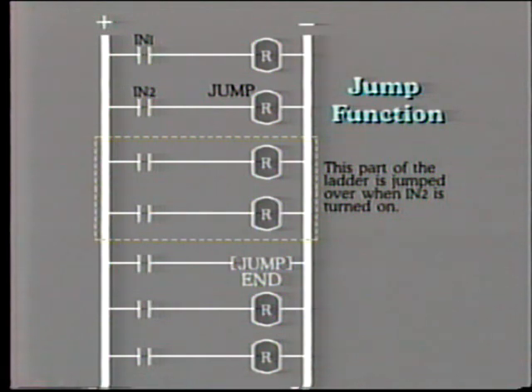Another very useful function, the jump function, allows us to skip over defined parts of the logic under certain specified conditions. This changes the response time of the controller, so be sure this is what you want to do.